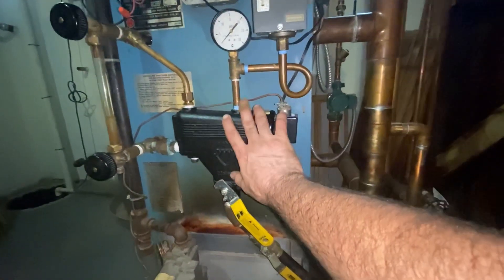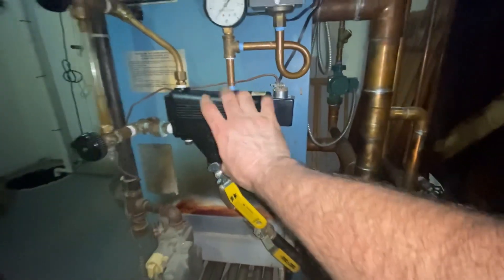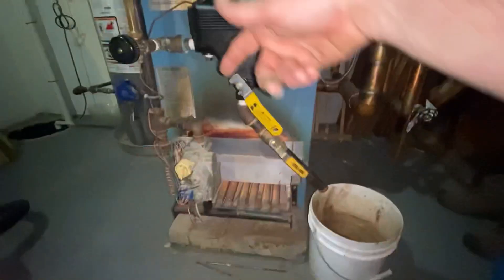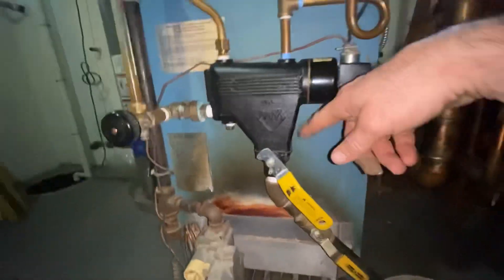When servicing this, you want to make sure it's on this McDonnell & Miller 67 low water cutoff. You want to flush out all the gunk and whatever's inside it. So I always have my boiler on. In your sight glass, you can see the water. So you drain it, go off, so it works.